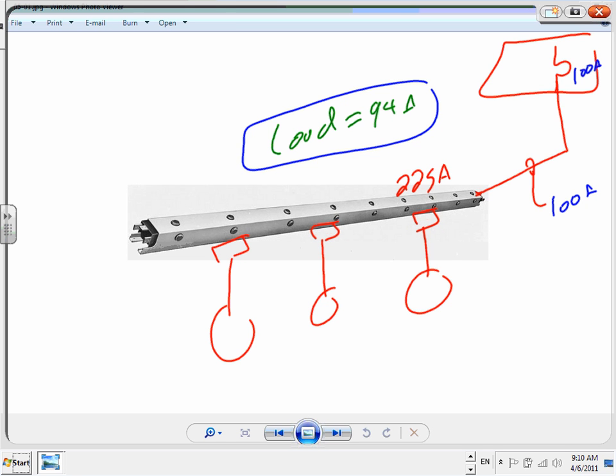It's like panels, guys. They don't make panels for every overcurrent protection device. So if they make a 225 amp panel, what if your load is 150? Well, if your load is 150 or less, you put a 150 amp circuit breaker in a 225 amp panel. That's okay, no problem. Who cares? Because that will reduce the size of the conductors and, of course, the price of the project.